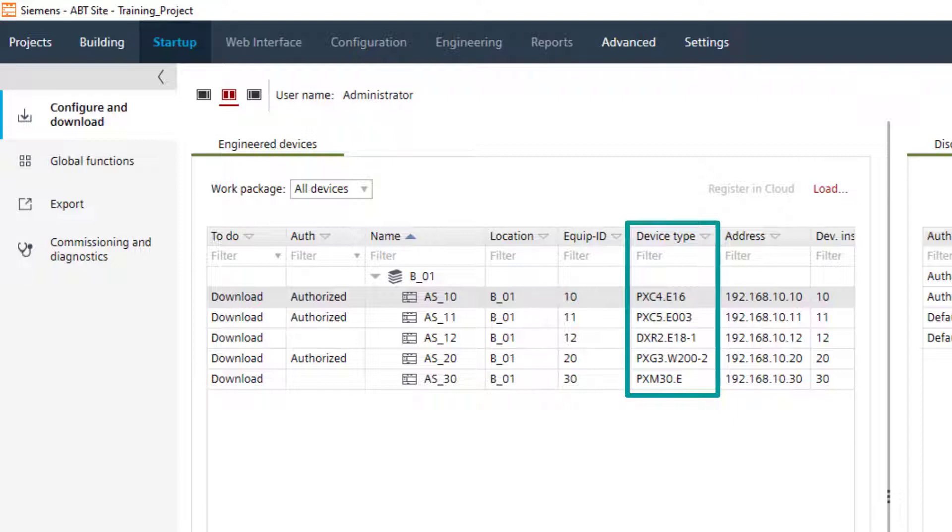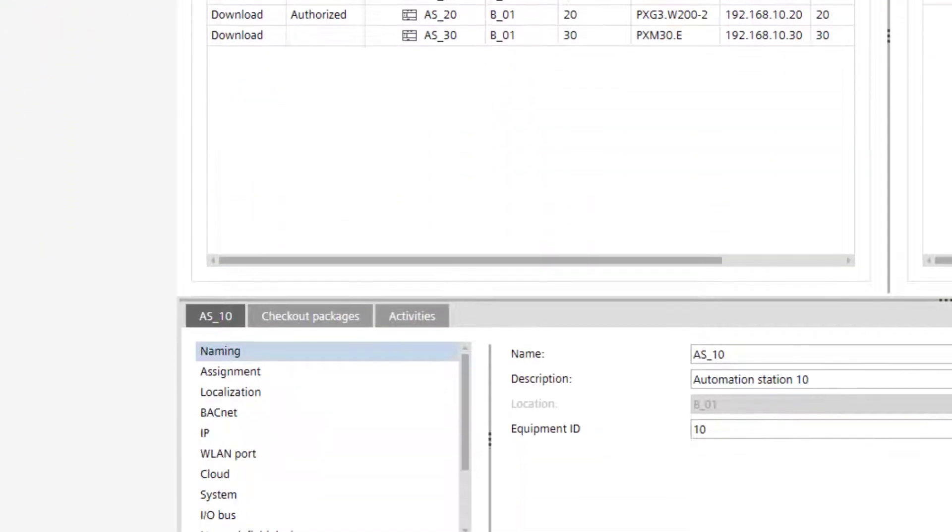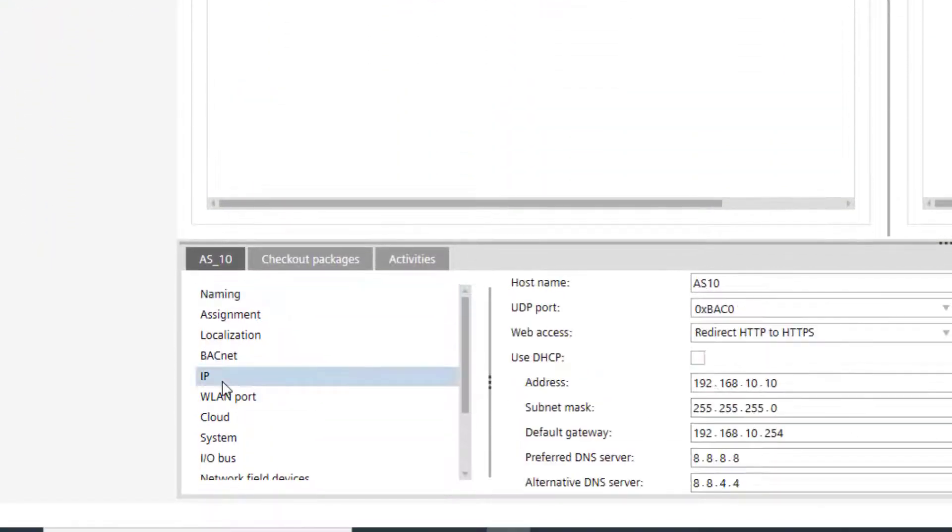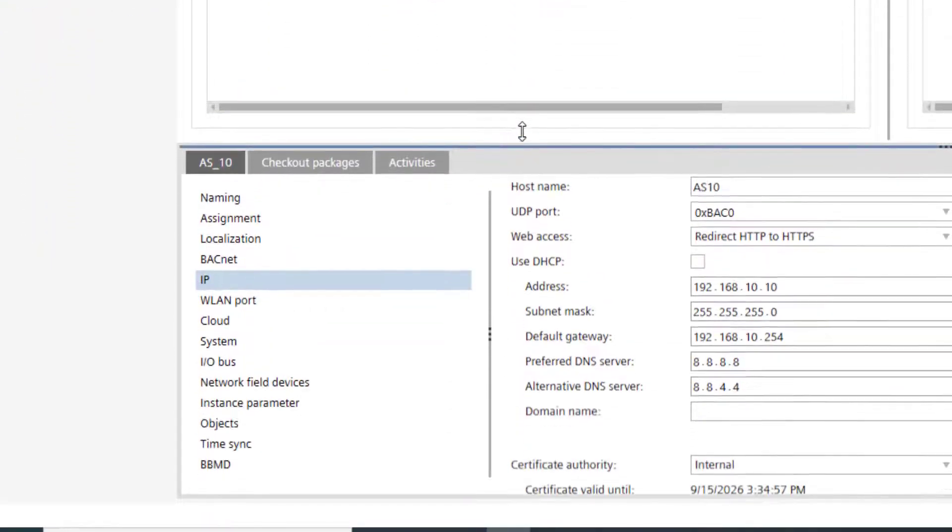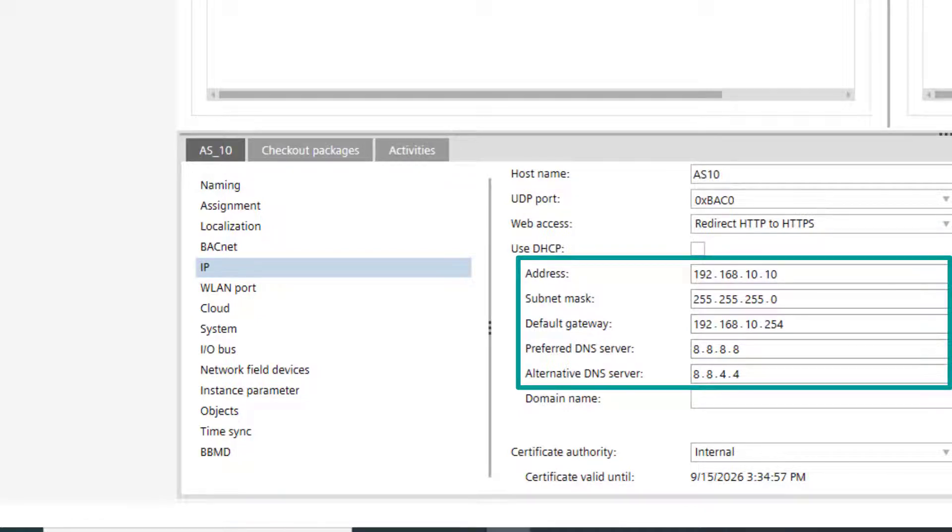The PXC4 automation station IP settings are configured in order to be able to reach a Siemens NTP server available over internet. So, a default gateway is defined, as well as preferred and an alternative DNS servers.